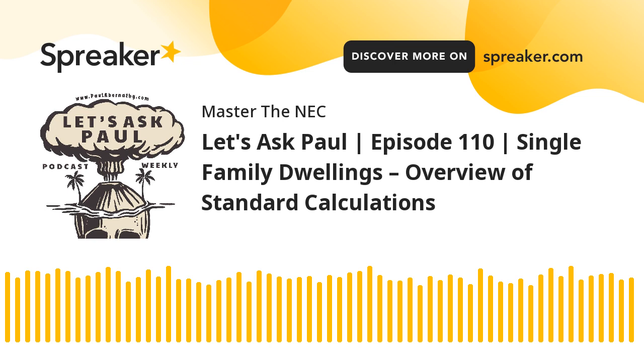Now, this table is interesting because we're only going to focus on the top part, and that is dwelling units, right? And so here you see dwelling units, and it says the first 3,000 at 100%. So you're just taking the first 3,000 at face value, at 3,000. And then it says from 3,001 to 120,000, or as I like to say, once you do the first 3,000, the next 117,000, because 117 plus 3,000 is 120. So since this second one goes up to 120, I like to say the next 117,000, you take it at 35%, okay? So that's at 35.